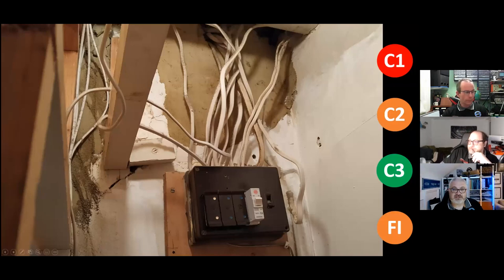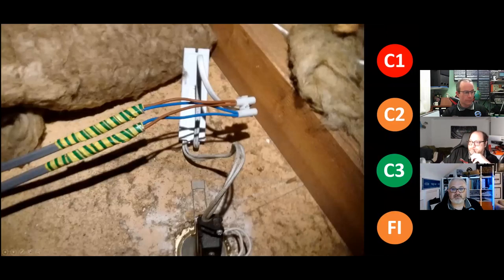So the results are in, yeah? C2? Yeah, great. C2. Moving on. All right, so we have a downlight here. A connection. Yep. This might be coming from the joint box we had earlier on. Yeah, I think we said it was a C2 there, wasn't it? Same principle, same issue. If we can agree that, I'll skip on. This will come up as a C2.